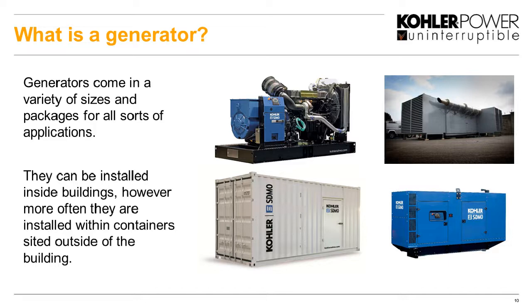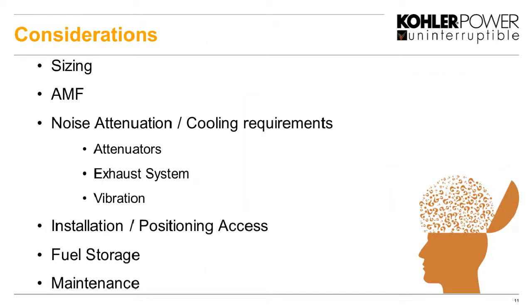Okay. So some of the considerations we have to make, and we go through these: the sizing of the generator, the AMF panel, and we have other things to consider like the noise, the cooling, exhaust, vibration and things like that, and we'll have a quick look at those things. Then we have installation and positioning, and of course the fuel storage for the generator as well. And we mustn't forget that maintenance is critical for generators as is for anything else, and we will have a look through that as well.